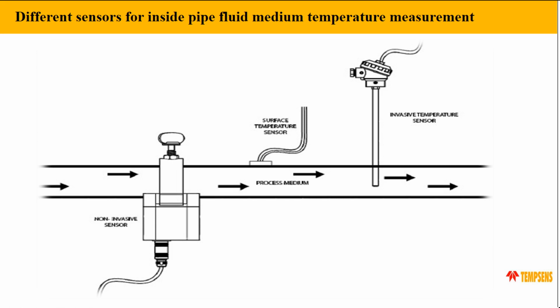Instead, to eliminate these problems, we can use a non-invasive clamp sensor. You just need to put this sensor below the pipe, check the temperature, then unclamp it and put it on another section. No process intervention, no drilling is required - you just clamp the sensor onto the pipe. I will show the schematic view of this sensor in the next few slides.